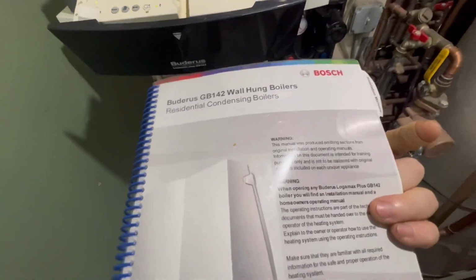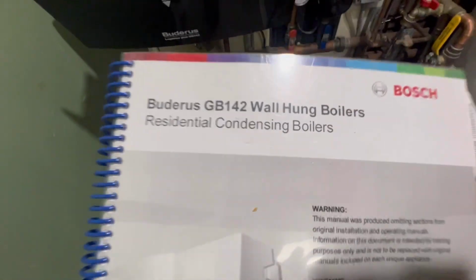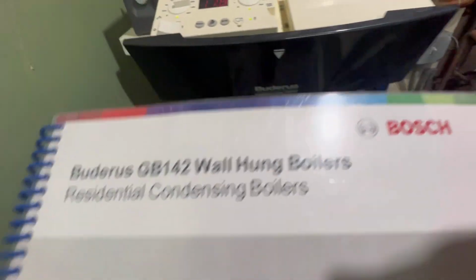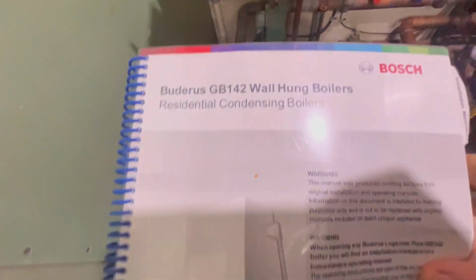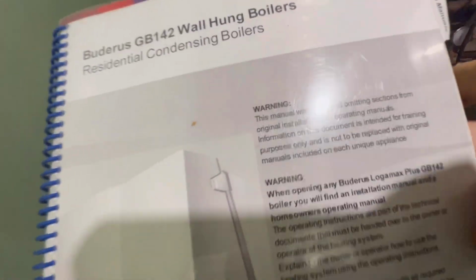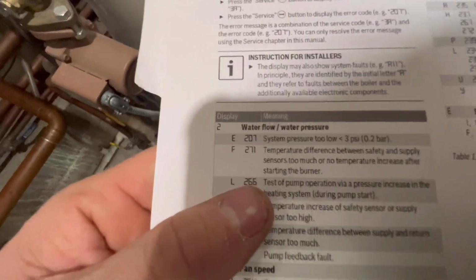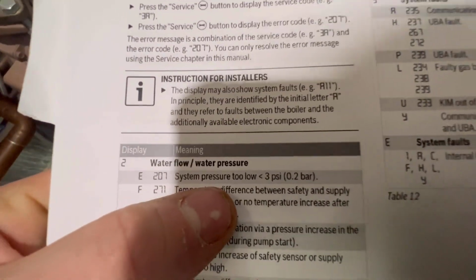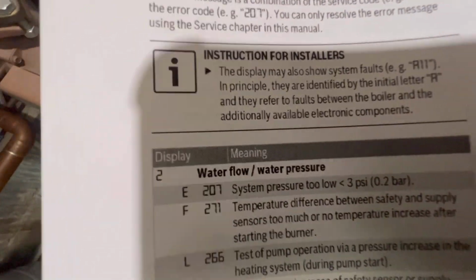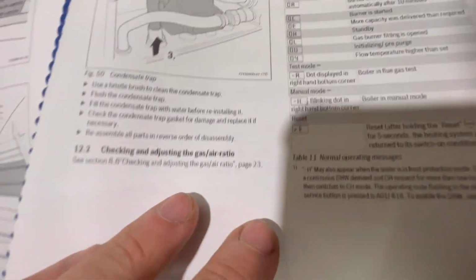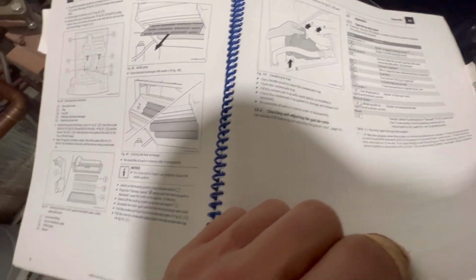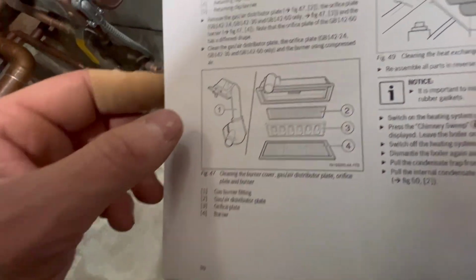Alright guys, so after digging in the truck, I do have the Buderus manual for the GB142 Logamax residential condensing boilers, and we're just gonna go and look at the error codes it's giving us here. 207, system pressure too low. We were getting a 207 code, and we were getting something else. But it tells you how to dismantle the heat exchanger.